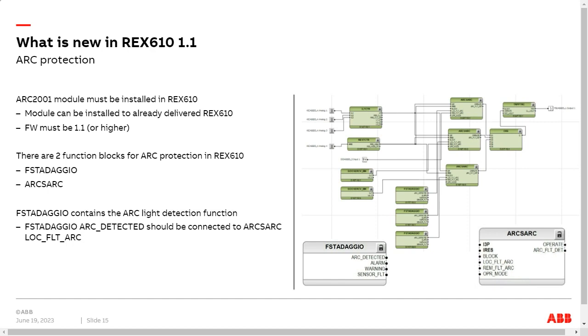But if you use the arc function, it's based on light only. If you want the dual criteria, both light and current, then you always need to go through the arc protection function.